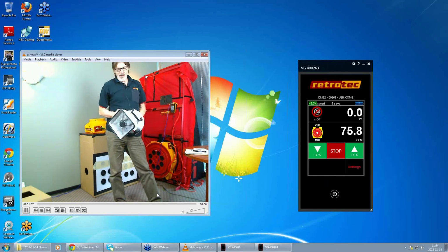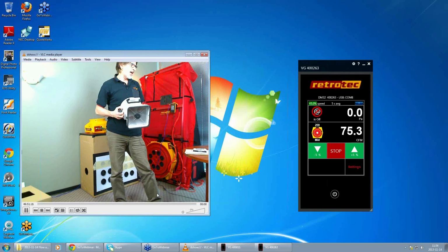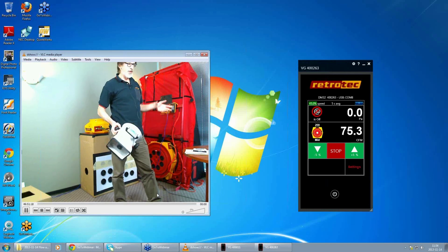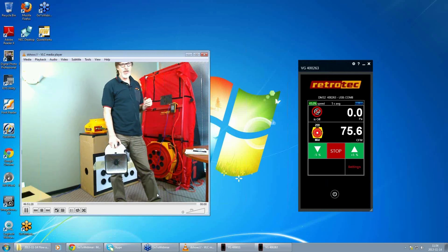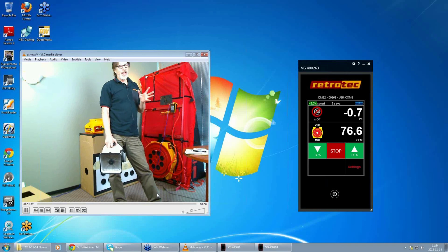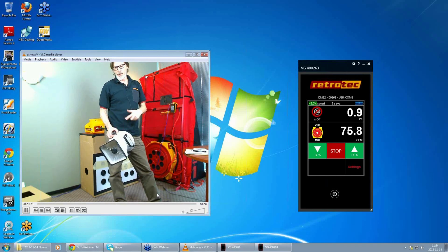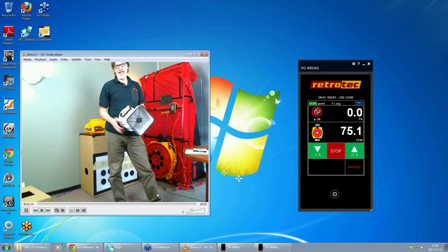It's a very special type of device which has particularly good results around 0. And the typical gauge, like our gauge or the Energy Conservatory gauge or anyone else that makes these high precision gauges, around 0, they're accurate within 0.15, 0.2 at best, 0.2 pascals. So this is probably 10 or 20 times more accurate in terms of zeroing, which allows us to do some pretty exotic testing with it.